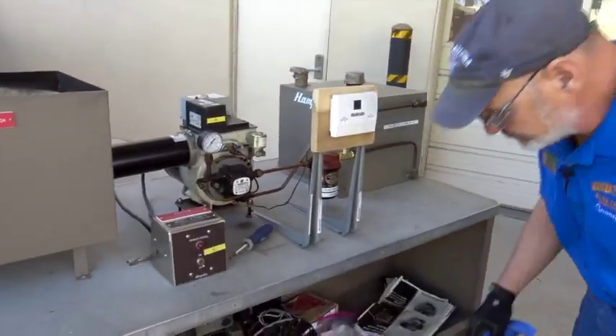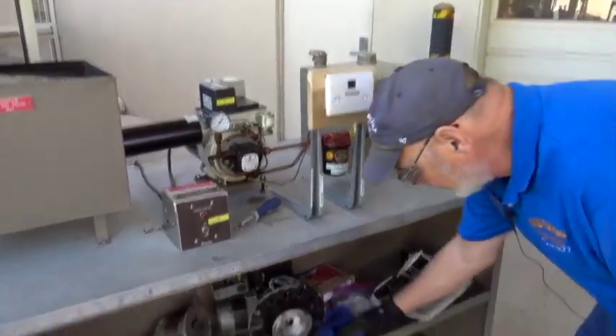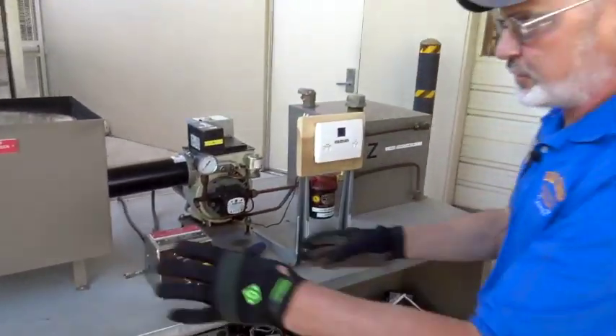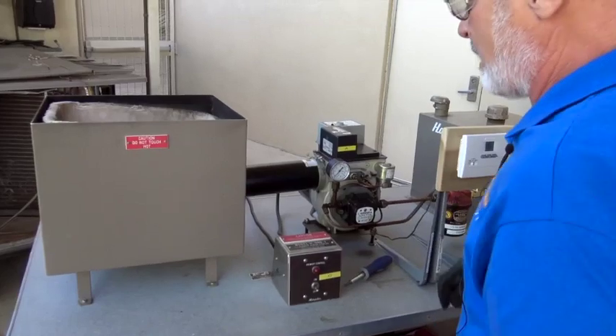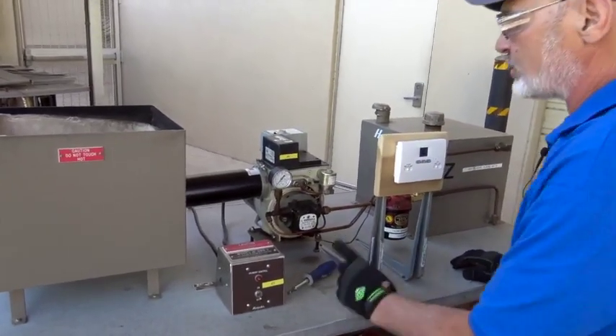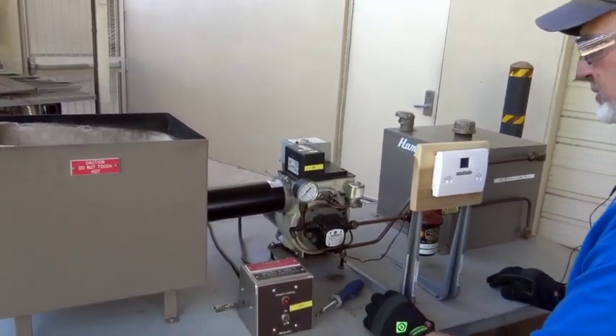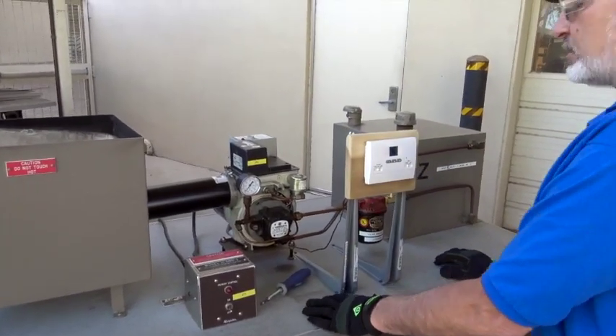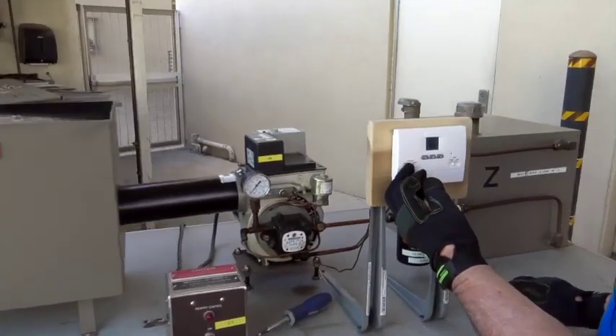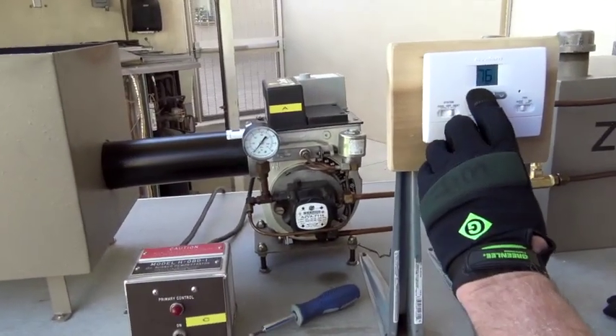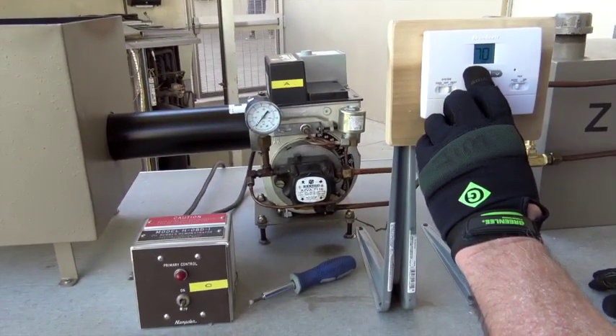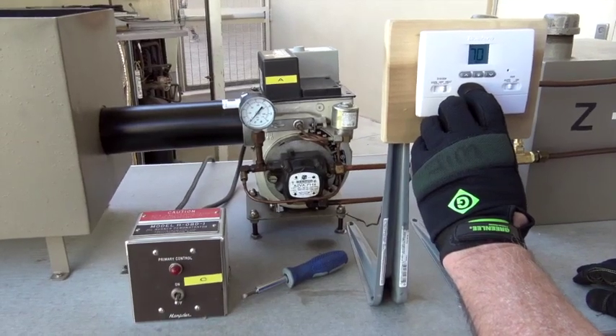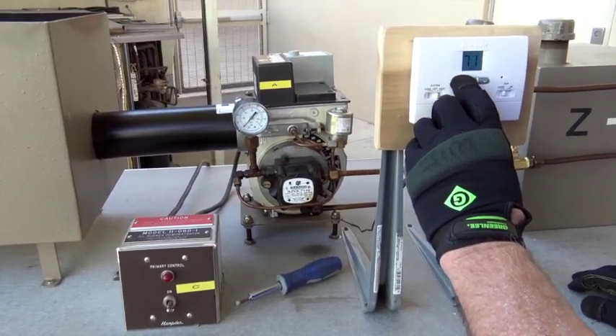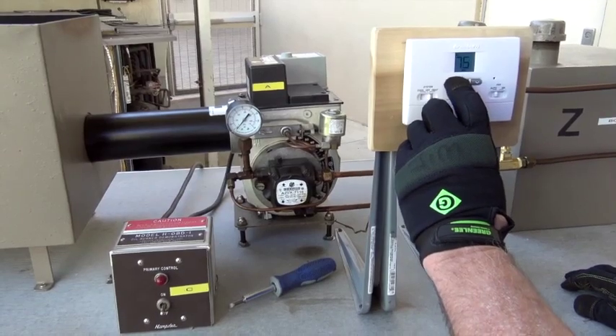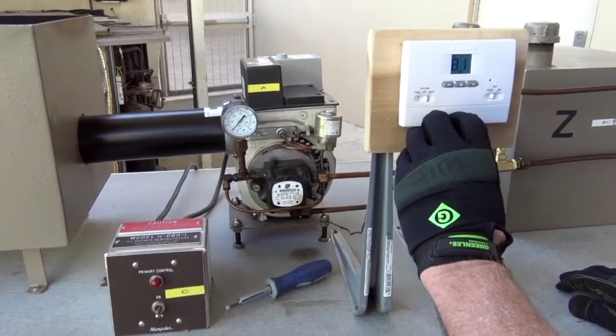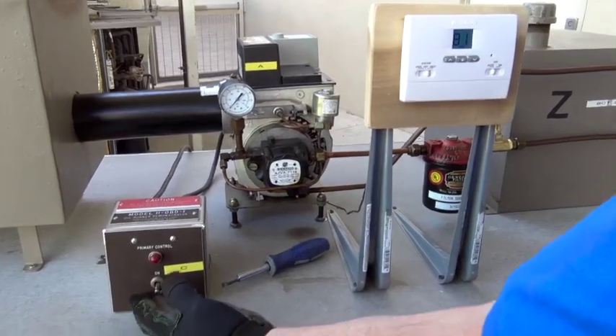Before we fire it up, we want to make sure we have no combustible things around the area, no newspapers, none of your books or anything, because this thing's going to take off. It's going to fire up. We're going to do it step by step. I'm going to show you the pressure on this thing as it calls for heat. Now I'm going to switch it over to heat, and then I'm going to hit the set point. Above 76, I'm going to go up to 81. Turn on the switch.